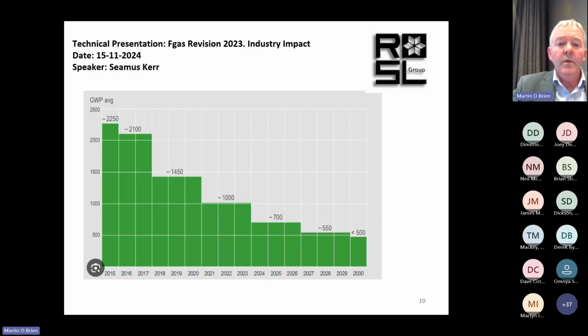So this was basically the story before the new regulation. On the left-hand side was 2015, where the average GWP of any refrigerant was going to be 2,250, which allowed for R404A and R507. Then, by controlling imports using customs controls, heading for 2030 we'd have an average refrigerant GWP of less than 500, and obviously much less refrigerant available.